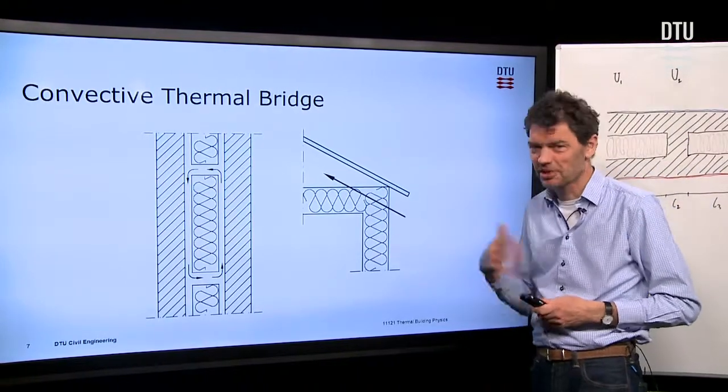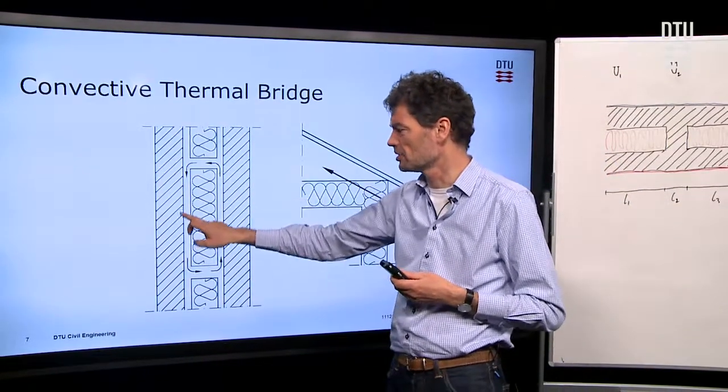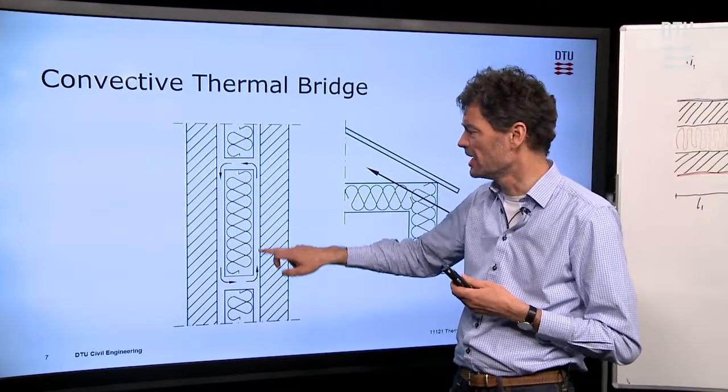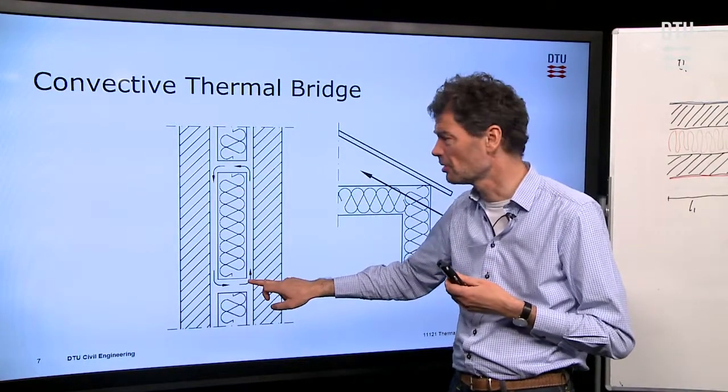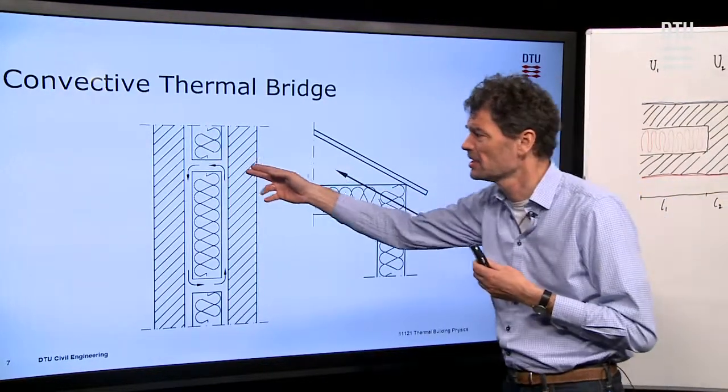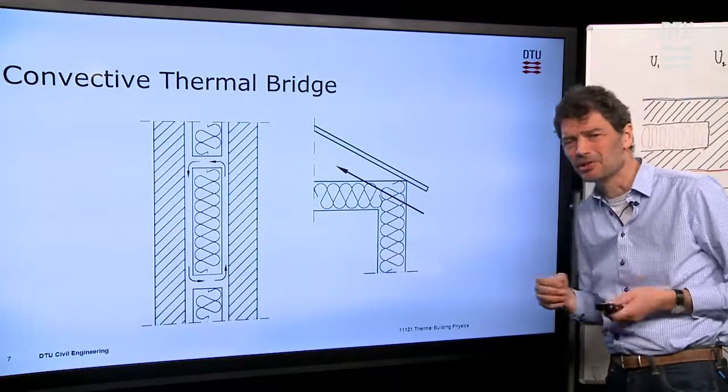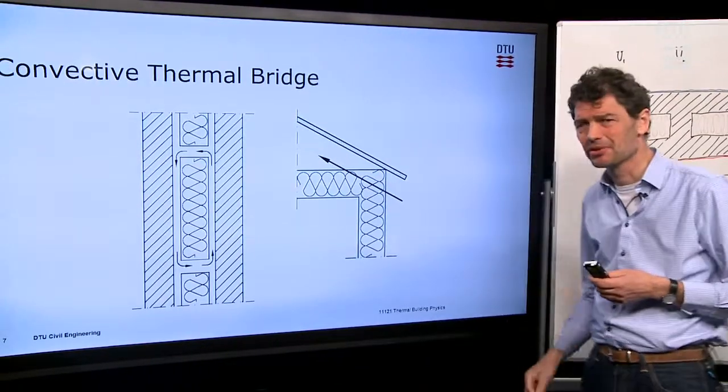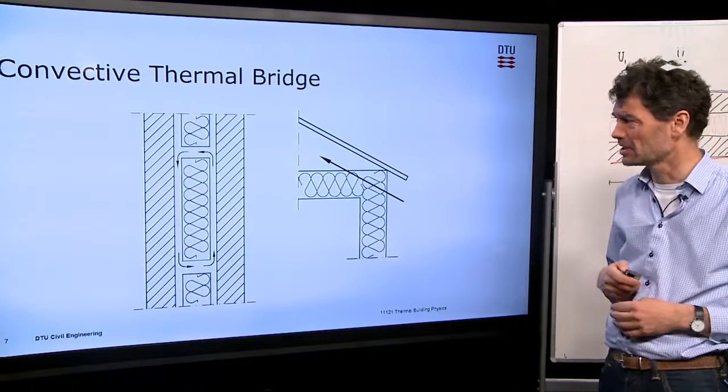The last type of thermal bridge that we also sometimes see is a convective thermal bridge. If there's some possibility for air to somehow pass around the insulation batts in a wall, then the air would be heated up. It would bring the heat to the front where it's cooled down, and then led back cold. So that leads to an extra thermal transmission, which kind of looks like a thermal bridge. It could also be air that passes through some other elements of the structure.